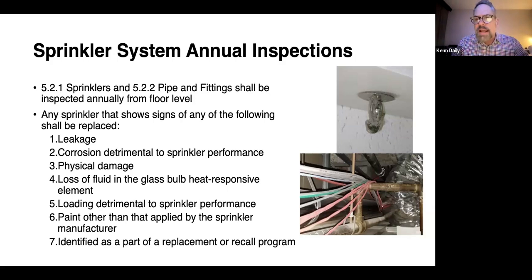Any kind of movement of the head, up, down. Any gap between the head, the escutcheon, and the ceiling is inappropriate. And then, of course, the other picture there is where wires are running across sprinkler pipe. You can never touch sprinkler pipe. Never. The other day, I was at another building, and they literally had zip tied.